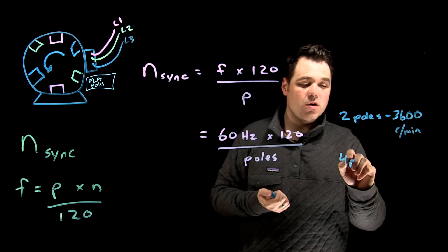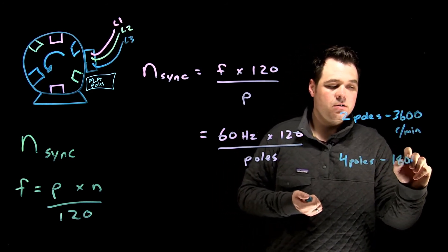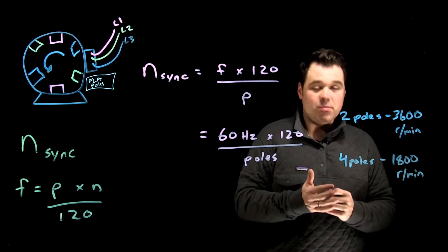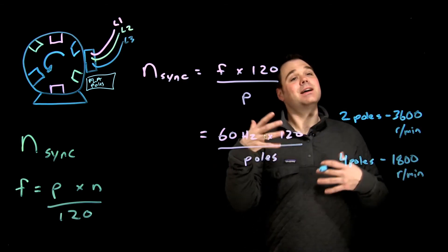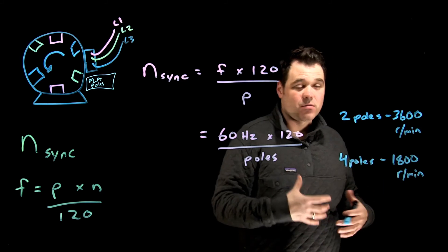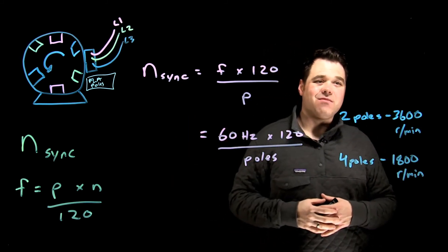A four pole motor, which is pretty common, would give us 1800 revolutions per minute. A six pole motor would be 1200, an eight pole motor 900, a 10 pole motor 720, a 12 pole motor 600. So it keeps going down like that, but the whole time I'm just using that formula there.